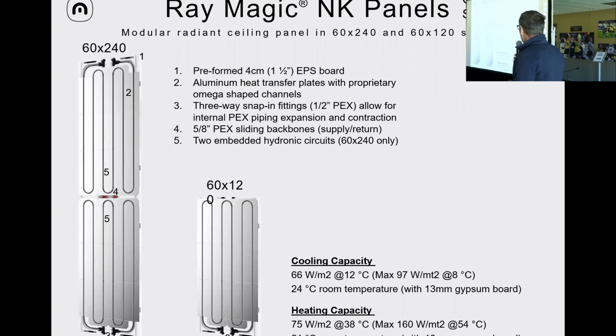The panel is made of this white pre-formed EPS, and that acts as a back insulation. The EPS is about 4 centimeters. On top of the EPS, we put the aluminum heat transfer plates, and those plates have an omega shape where we insert the pipe. There are 2 serpentines in this panel: the first one goes in and out through these 3-way fittings, and the second serpentine is this one. Inside the panel are embedded the supply line that goes all the way down here and the return line. The lines inside are 5/8 PEX, 16 millimeter PEX. Part of the technology and the patent is these three-way fittings. The smaller size, 60 by 120, only has one serpentine.